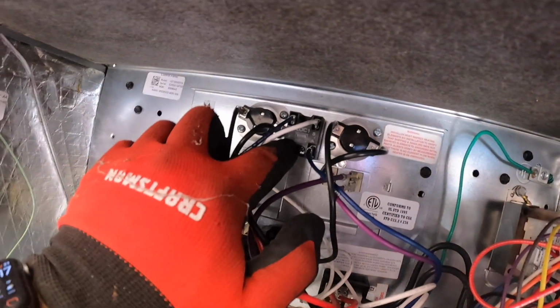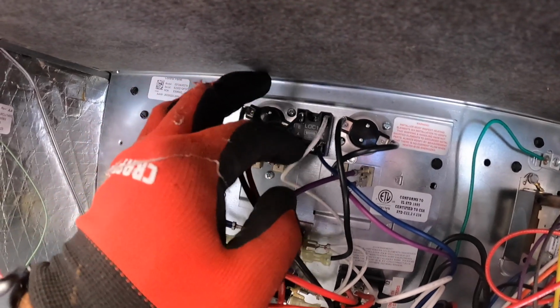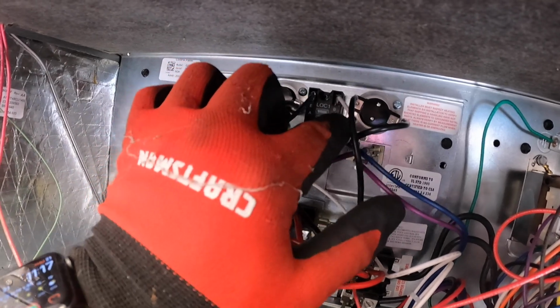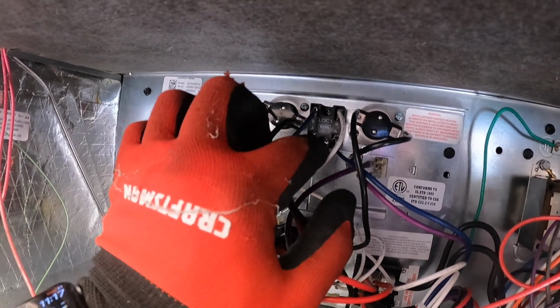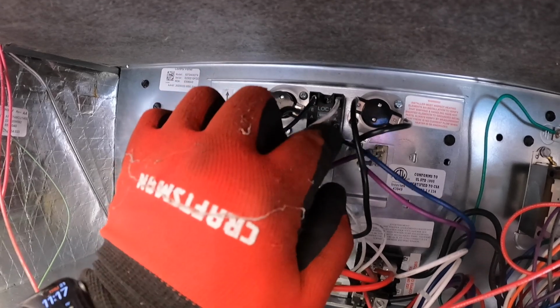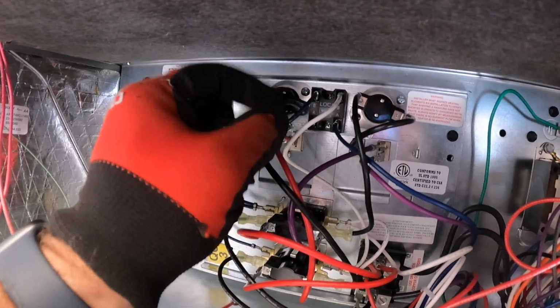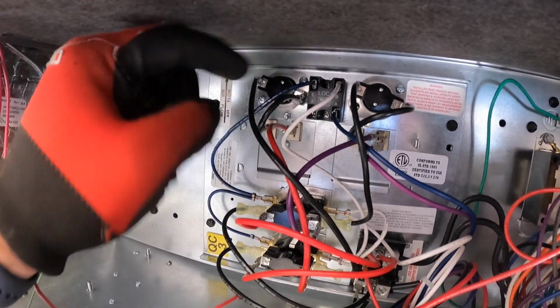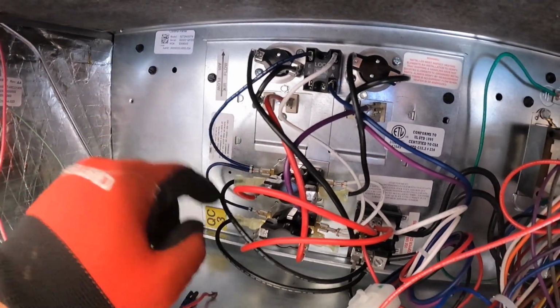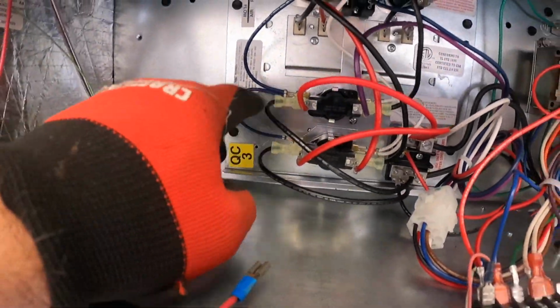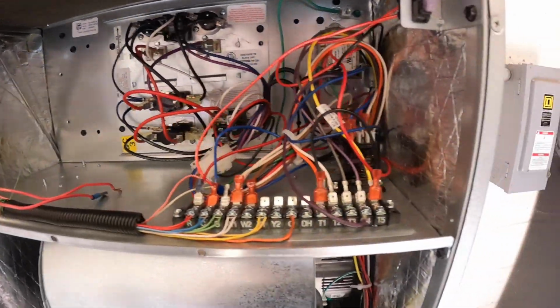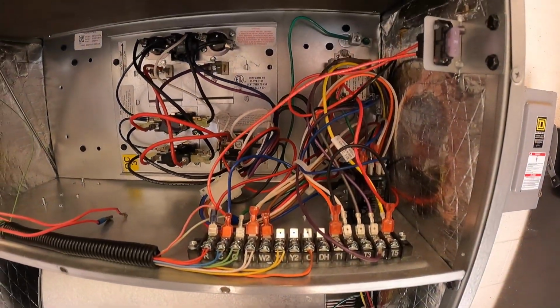This is a little limit that locks it out until you reset the power. These limits will reset themselves when they cool down. If this one gets too hot, you'll have to kill the power at the breaker in order to get it to come back. So I'll go ahead and pick it up on the side going in rather than the side coming out, because that's what it breaks. It looks like it breaks the common going to your sequencer switches down here. So that's pretty much it for in here on wiring.